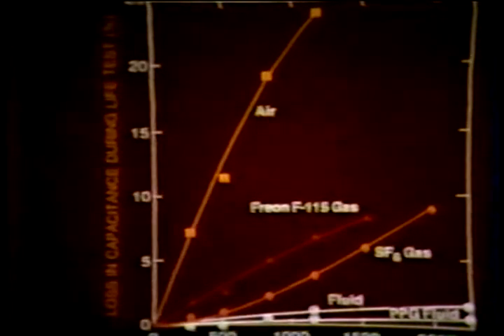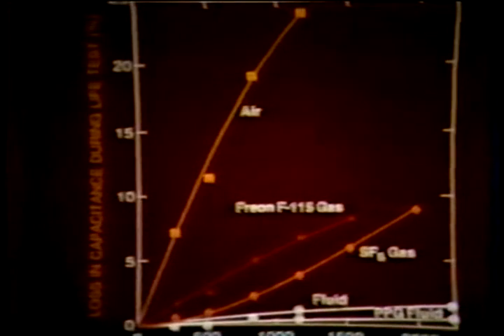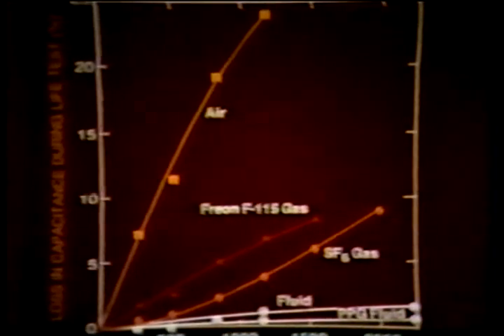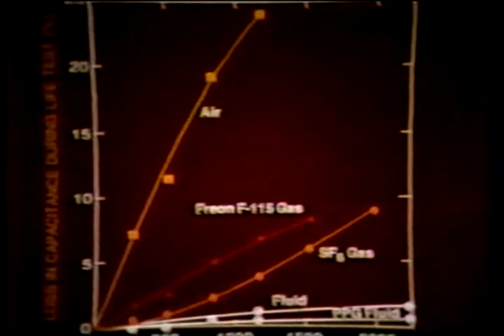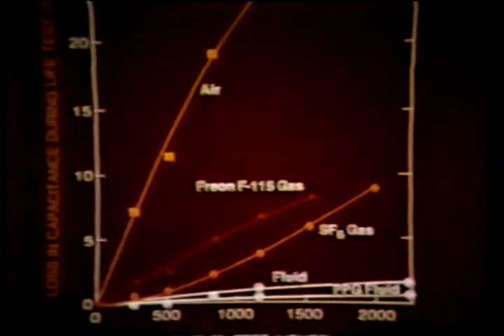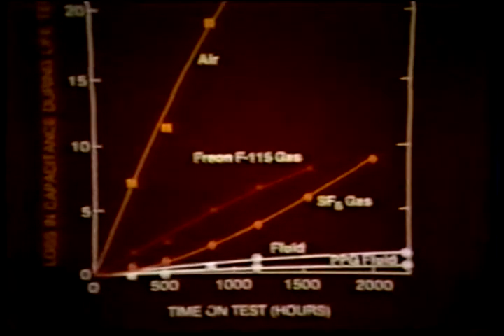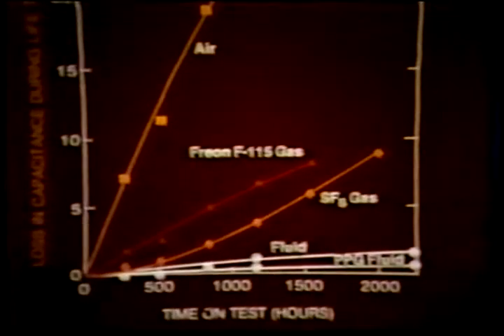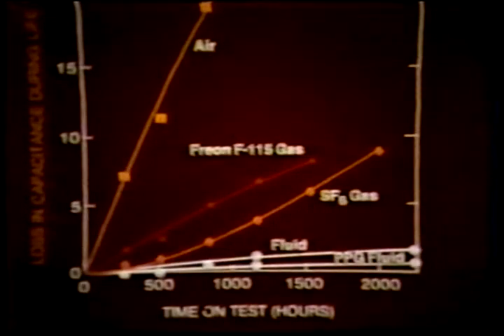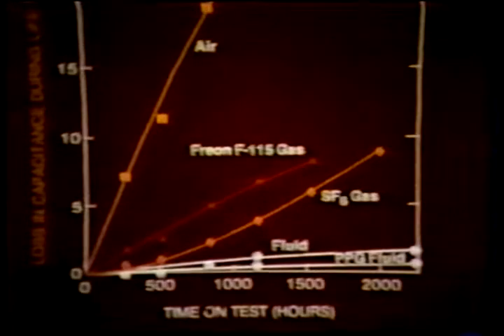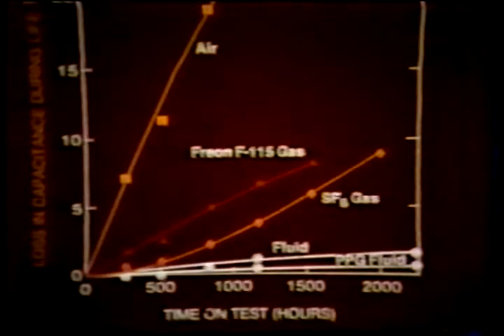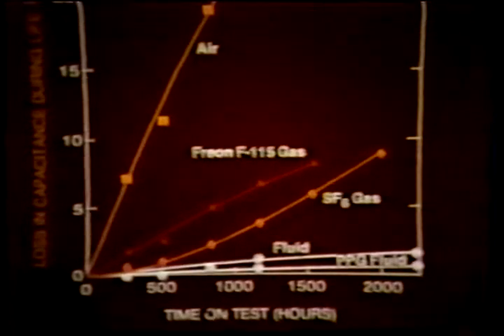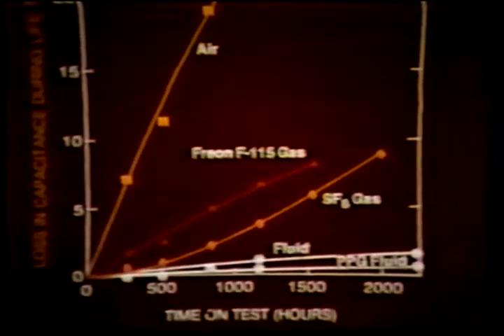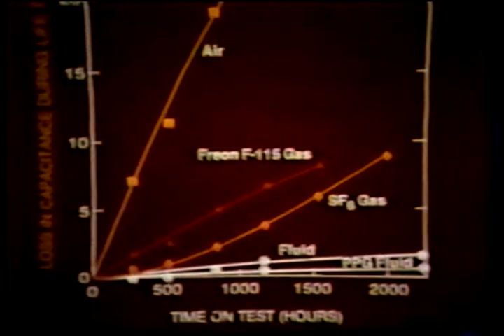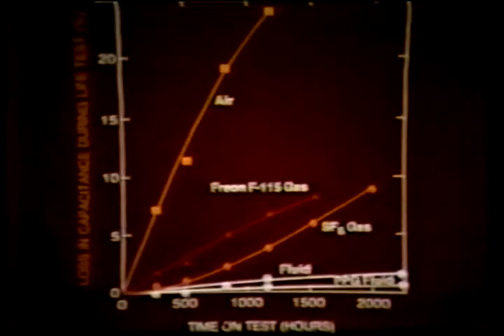We can see that the number of clearings can be reduced and the capacitance stability improved by a high-strength gas, such as SF6 or Freon. The most effective way to quench the partial discharges and clearing activity is to fill the capacitor at the edge and in the outer turns with a high-strength liquid, such as polypropylene glycol. For this reason, we find that most low-voltage metallized capacitors are constructed with a fluid surrounding the roll. This is especially true for those operating in the upper part of the low-voltage region. It is likely, however, that as we learn more about these partial discharge mechanisms, the dry, air-filled capacitors will be able to be used at higher voltages.